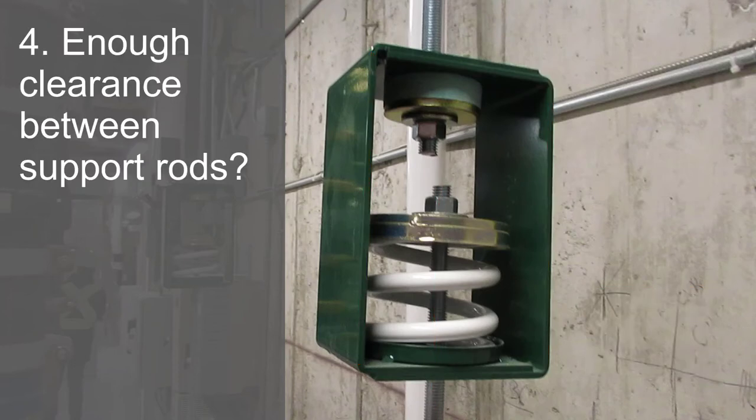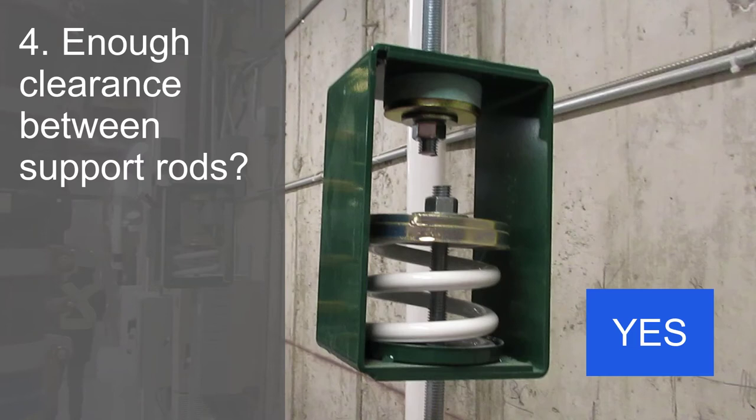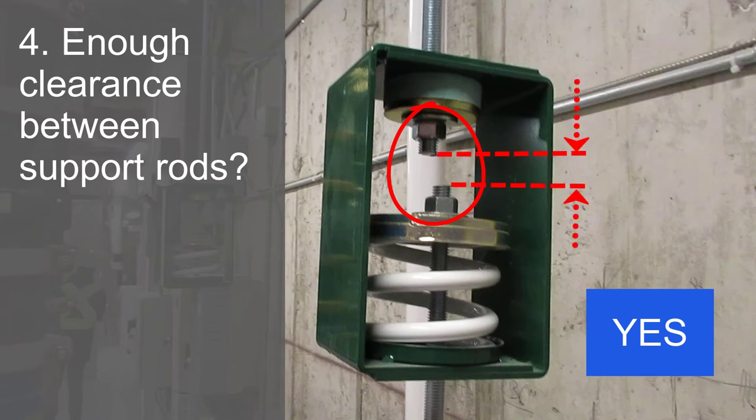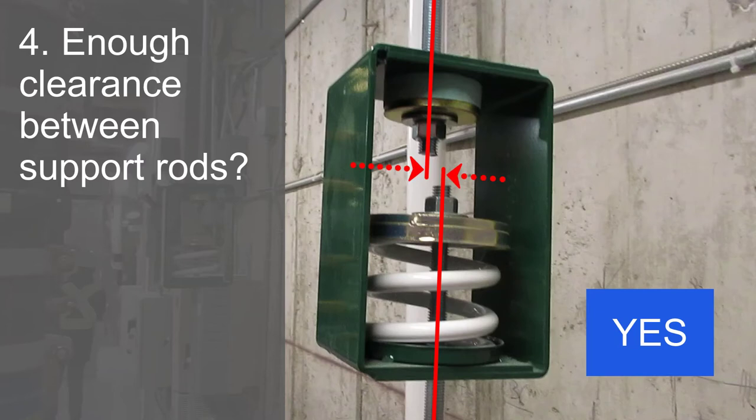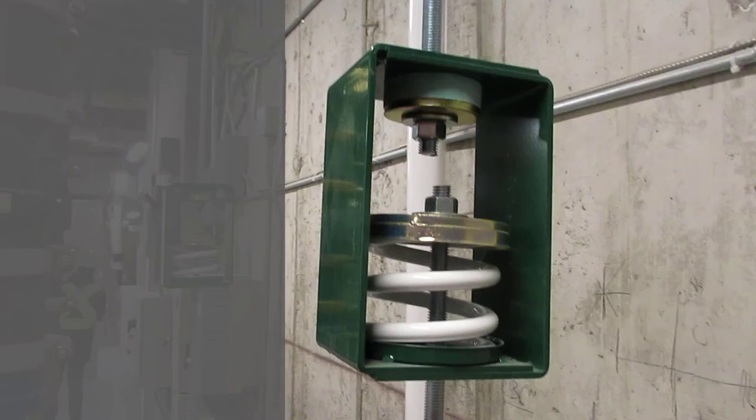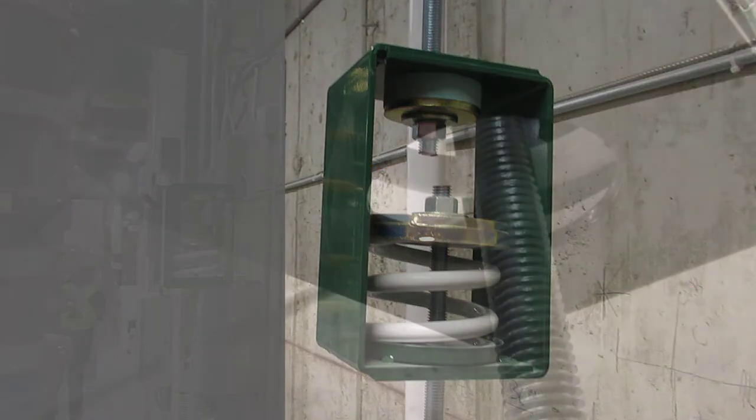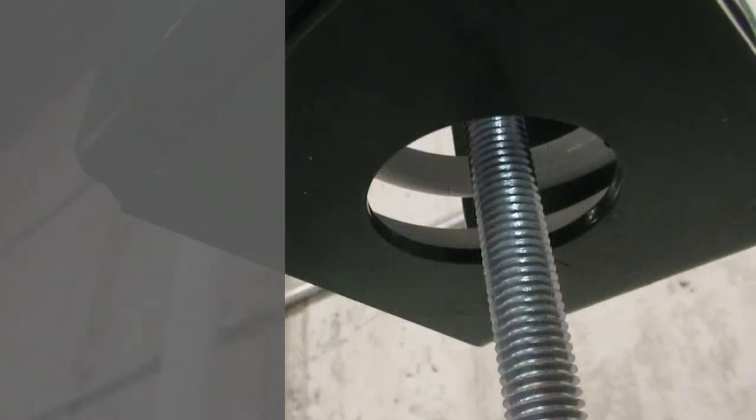Fourth, is there clearance between the upper and lower support rods? Yes. I asked this one because you can tell from the ends of the rods that the contractor used option A from the installation instructions. The rod was cut and a section removed to install the isolator. It is important that there is no short-circuiting from one rod to the other. These rods are slightly offset, but that's okay. We want to make sure there is no metal-to-metal contact of the rods to each other or to the hanger box, which leads us to the next question.